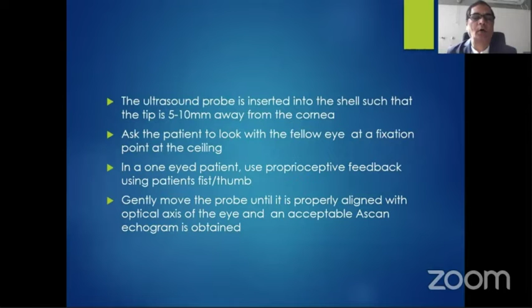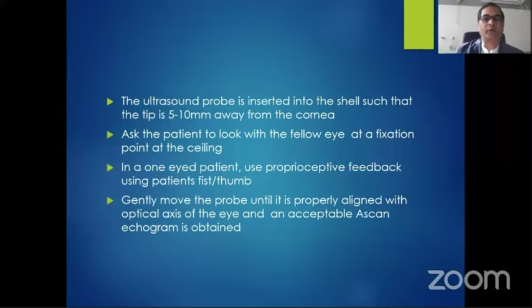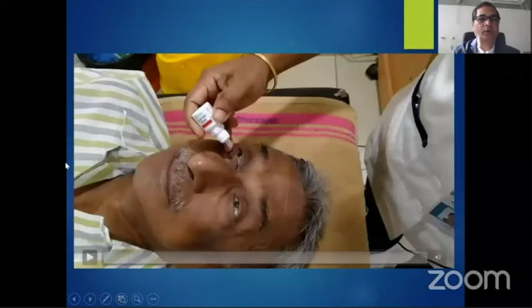Ask the patient to look with the fellow eye at a fixation point or at the ceiling. In a one-eyed patient, you can use proprioceptive feedback like a thumb or fist. Gently move the probe until it is properly aligned with the optical axis of the eye and an acceptable A-scan echo is obtained.